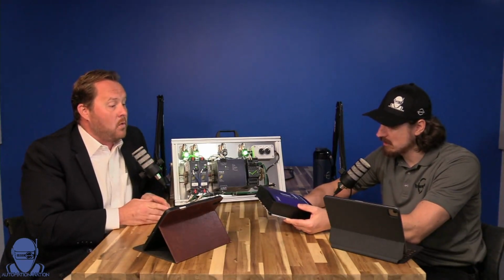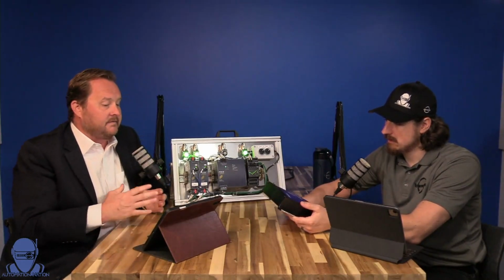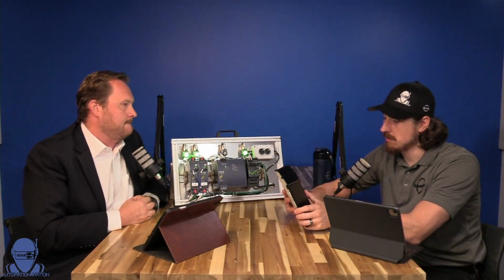So you can modify the current and the voltage going out for each individual output, and then you said it's an electronic circuit breaker too? Voltage would be for the entire device. Okay. Each output is independently configurable. And you can monitor the output from the face of the field-mounted power supply, the device as a whole, up to 15 or 25 amps, or for each individual output. When you're monitoring the outputs, you're monitoring the percentage of the set point. So if you set it to 8 amps and you're reading 30%, you're running at 2 amps. Sure. So you can monitor the load on each output, which is pretty nice.